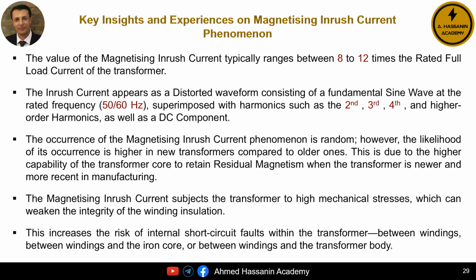The third point is that the phenomenon of magnetizing inrush current occurs more prominently in new transformers than in older ones. This is because a newer and more modern magnetic core can retain residual magnetism more effectively than older transformer cores. The fourth point is that since the magnetizing inrush current can reach up to approximately 10 times the rated full load current of the transformer, this results in mechanical stresses on the transformer. These stresses can lead to the displacement of internal windings from their original position, potentially causing short circuits between the windings themselves, between the windings and the magnetic core, or between the windings and the transformer tank.